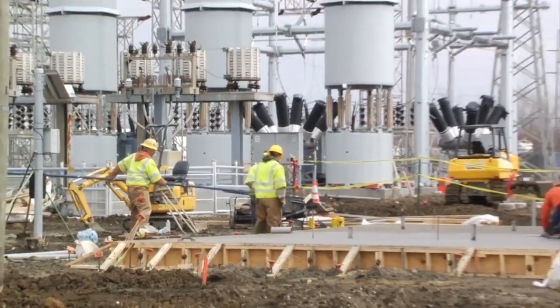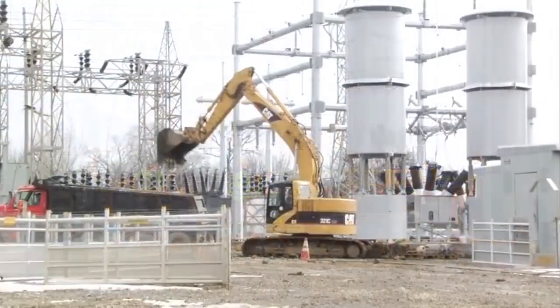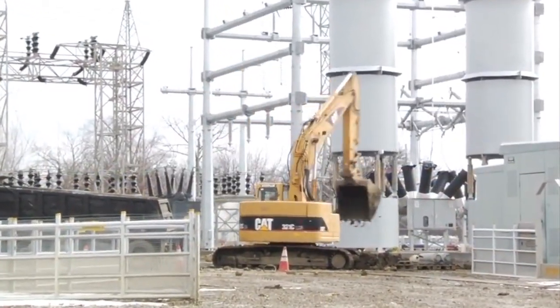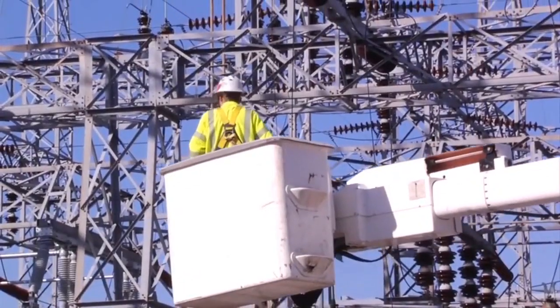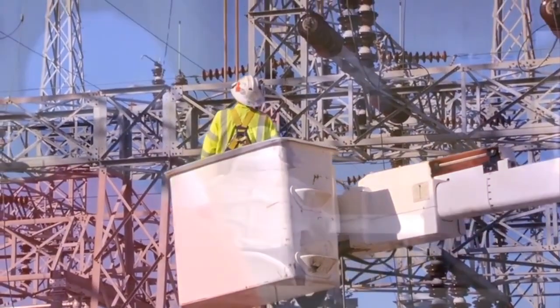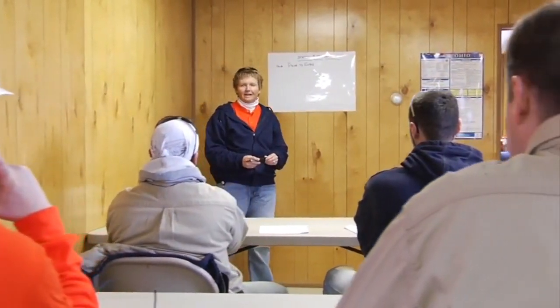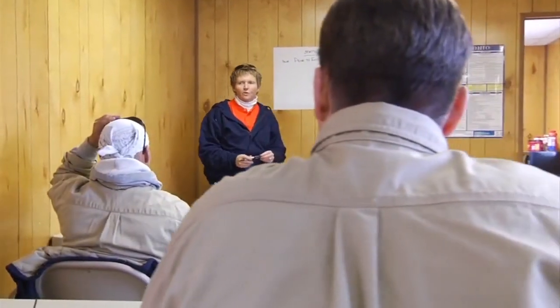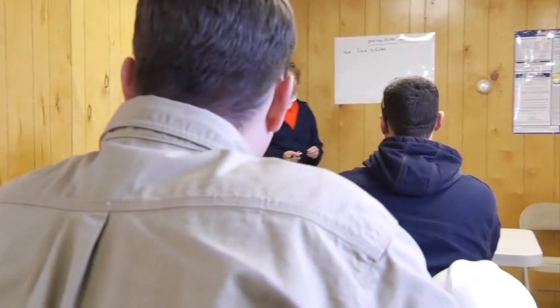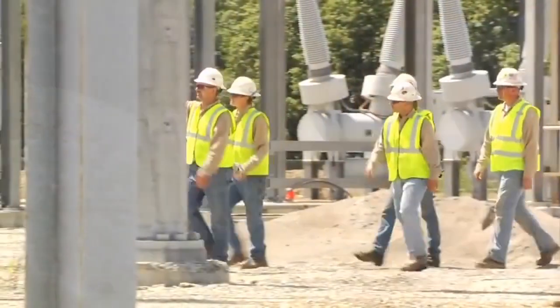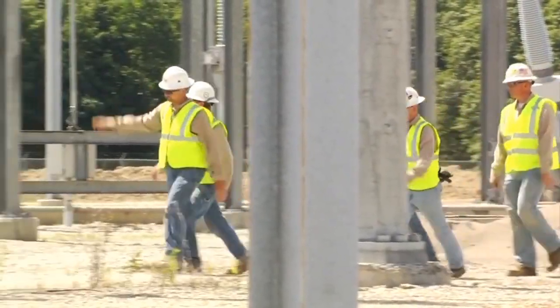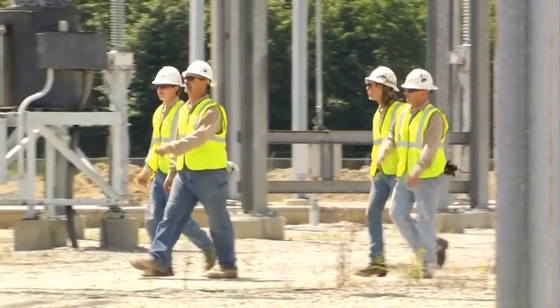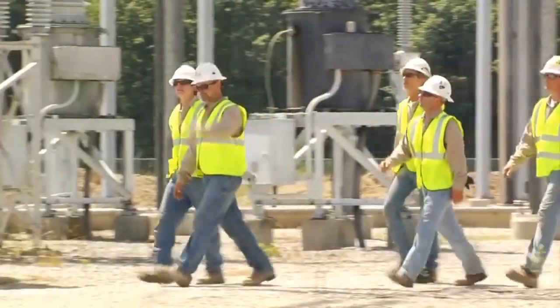Working in substations or switchyards poses unique hazards. With up to 765,000 volts nearby, you want to pay attention to AEP's safety expectations. Prior to entry of an energized substation or switchyard, all contractor personnel are required to complete OSHA-approved station entry training. Personnel who are not station entry qualified shall be accompanied at all times by a qualified supervisor.